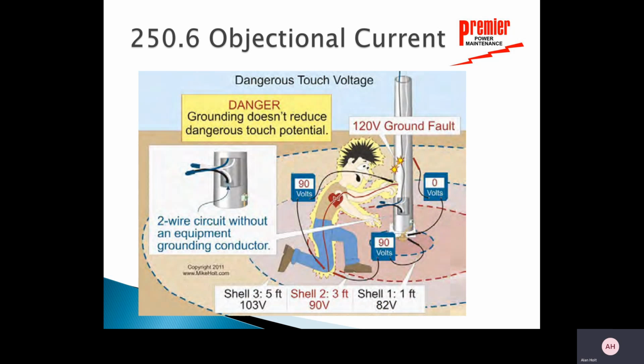Objectionable current, dangerous touch voltage. So here's the situation I get into if I don't have a good solid ground. It doesn't necessarily reduce dangerous touch potential. So I can have a 120 volt ground fault right here. Okay, I can have that right there. I can have 0 volts from this pole to the ground that it's attached to right here.